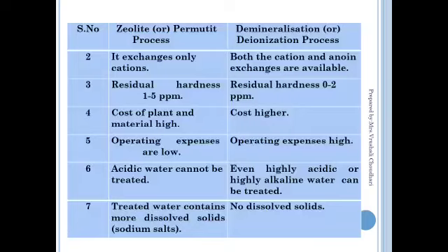For zeolite, the cost of material and plant is low, but ion exchange is quite a higher cost. Operating expense for zeolite is low, for ion exchange it is high. In the zeolite process we cannot use acidic water, but in ion exchange we can use acidic as well as alkaline water. Dissolved salts will not be present in demineralized water.